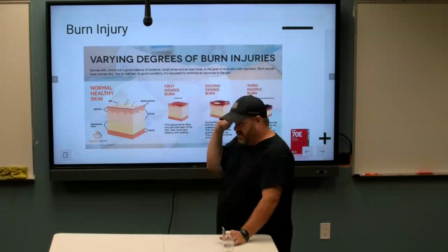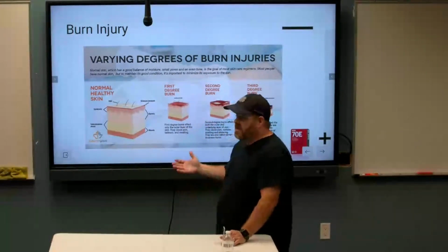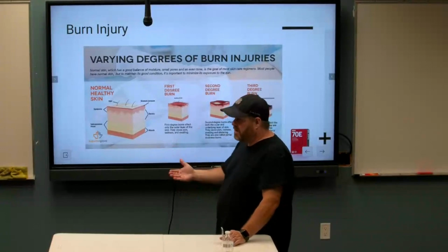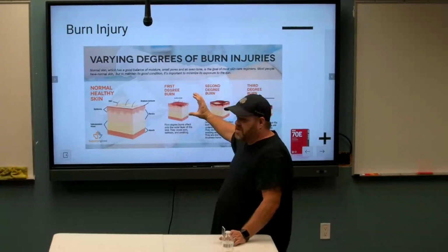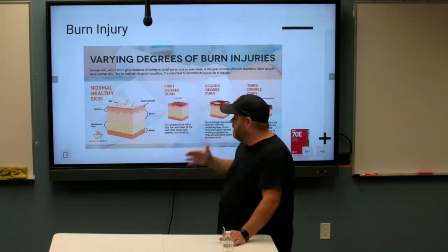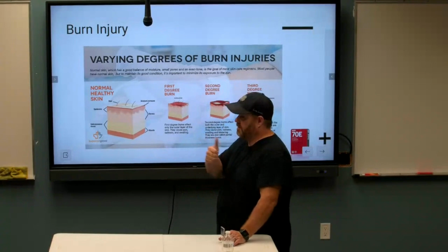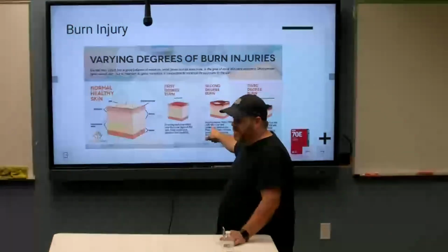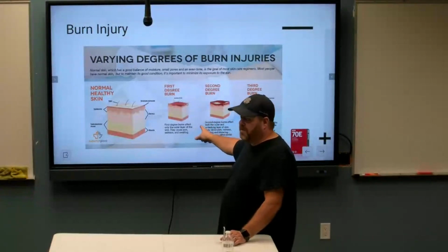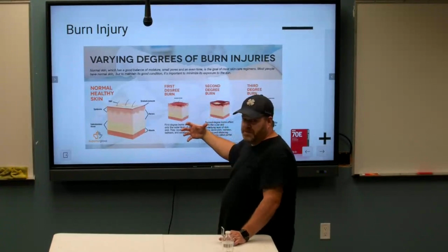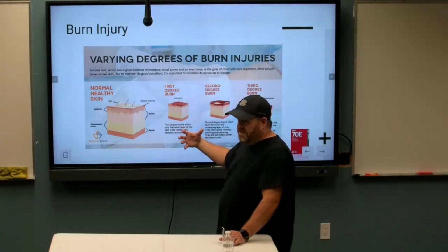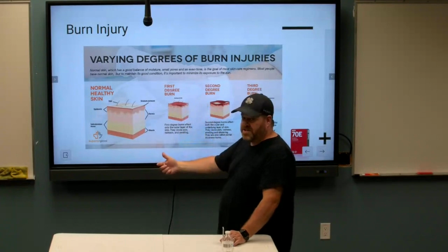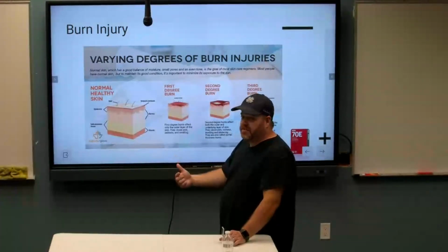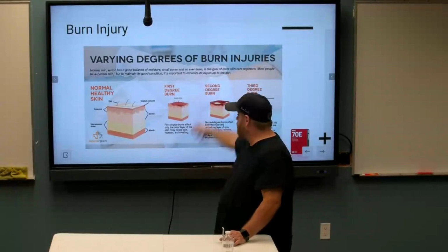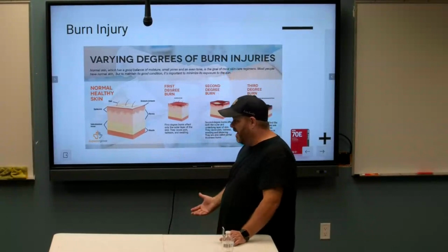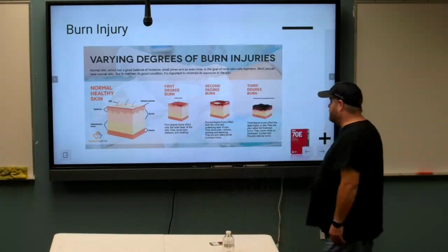Exactly. That's why you know all the answers, because you're here. No offense. Anyways, if you're wearing arc flash PPE and it's properly rated for the amount of exposure and calories per centimeter squared of arc flash, it's designed to hopefully limit your burns to a second degree and hopefully keep you alive. So if you're in an arc flash wearing the properly rated PPE for that equipment, you're not going to go home and pop a cold one and say, guess what happened at work, honey. It's not going to happen. She's going to go to the hospital, she's going to be visiting you there. It's only designed to hopefully keep you alive and hopefully limit your whole body burns to a second degree. Crazy, right? A lot of people wear arc flash PPE with a false sense of security.